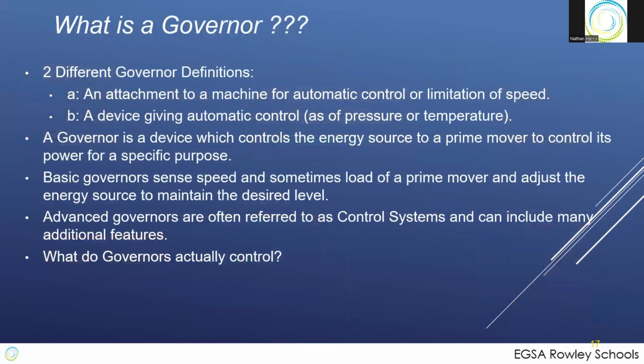But a governor really is set out to maintain or limit a function. In this case, most often it's speed. The voltage regulator does the volts, the governor does the speed. And the question for you is, and again, I don't read every word, feel free to read this as I go along: what does the governor in these systems actually affect in the system? What's the output of the governor actually doing? Increases what? Anyone? If the AVR controls the excitation, the governor controls what actual physical quantity?